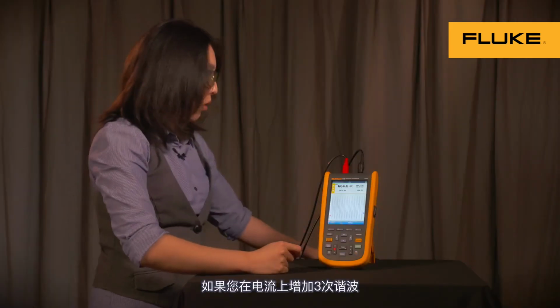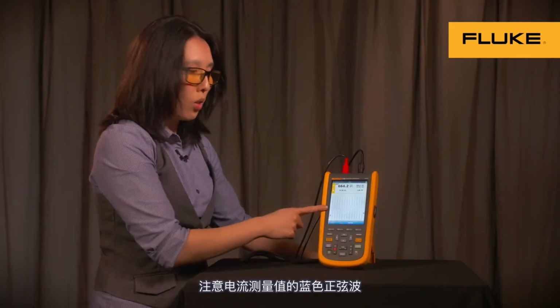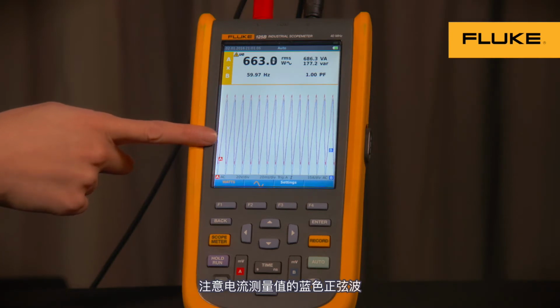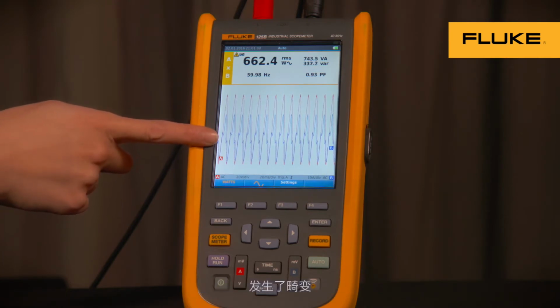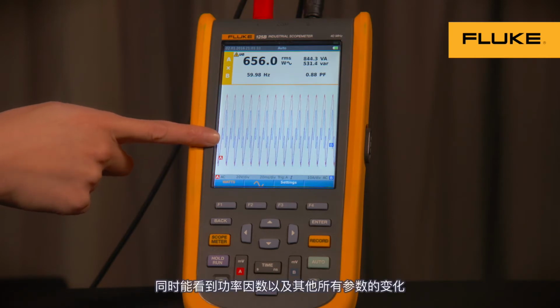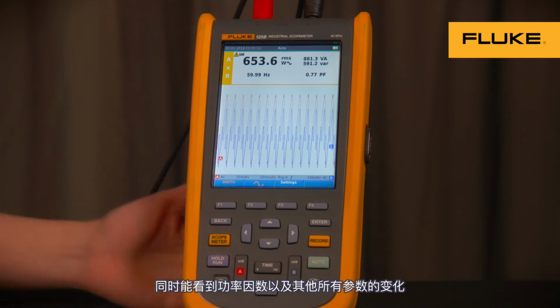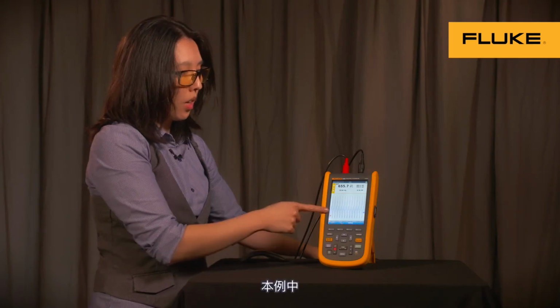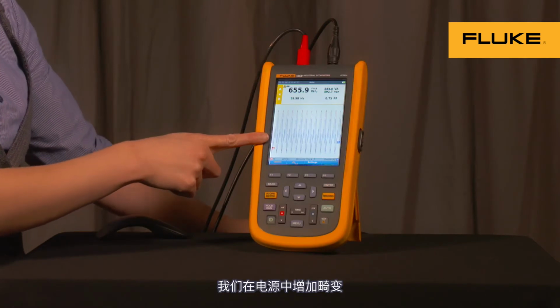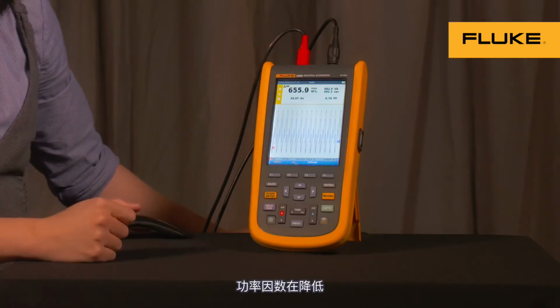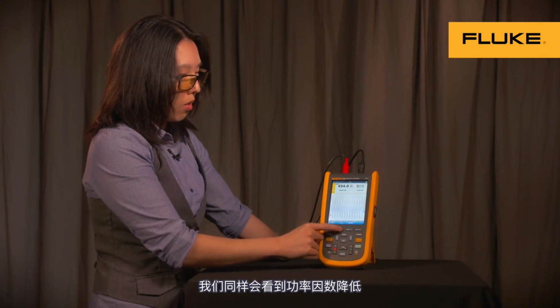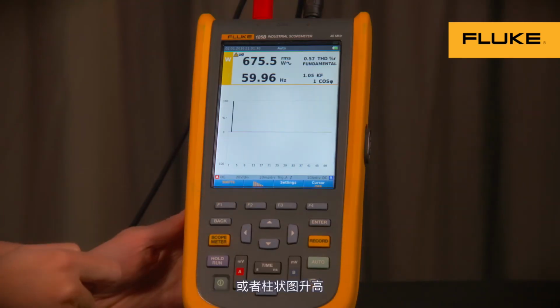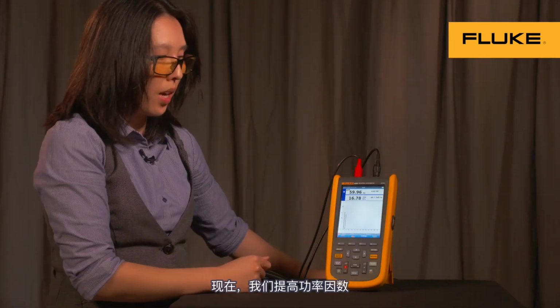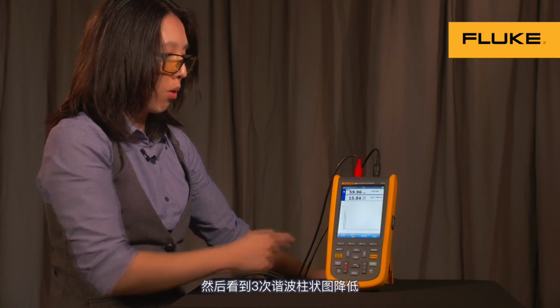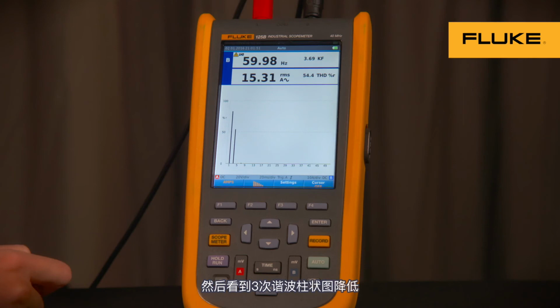If we add a 3rd harmonic distortion on the current, notice the blue sine wave, which is our current measurement, experience distortion. And at the same time, you can see your power factor and all your other power parameters change. In this case, we're adding distortion to our supply. So that means our power factor is decreasing. You can also see the histogram bar of this if we go to current display. And now let's improve our power factor and watch our 3rd harmonic bar decrease.